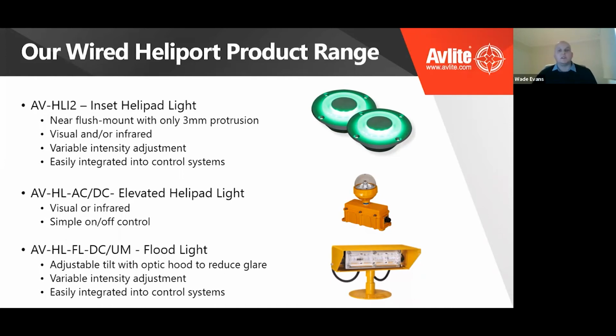That means you can provide NVG guidance for those using NVG goggles while also maintaining visual indication, all in a single fixture without needing to select between visual or IR. It all comes together in one. Variable intensity adjustment has a 0 to 10 volt feed, allowing control with high resolution and catering the intensity to the desired needs of the implementation. It's easily integrated into control systems with direct wired connections, and it's really what's leading the way in terms of our movement and trends within the industry.